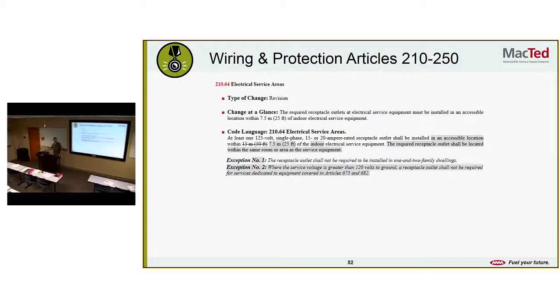Revision, electrical service areas. There's a revision to electrical service areas. The required receptacle outlets, the electrical service equipment must be installed in an accessible location within 25 feet of indoor electrical service equipment. So it looks like the code change, the language change was for that outlet, at least a 125 volt single phase 15 or 20 amp rated receptacle outlet shall be installed in an accessible location, 7.5 meters or 25 feet from the indoor electrical service equipment. The required receptacle outlet shall be located within the same room or area as the service equipment. So that's what they updated.